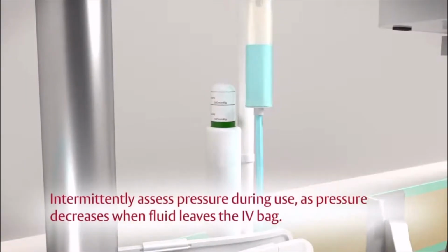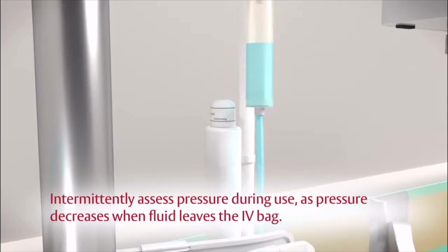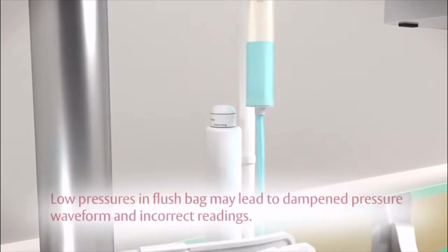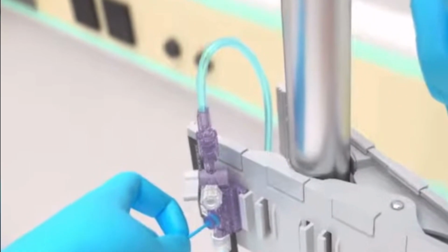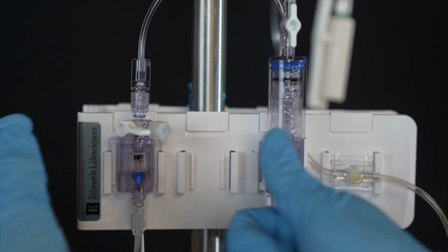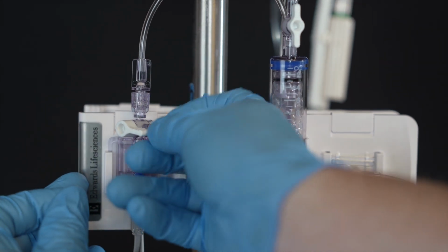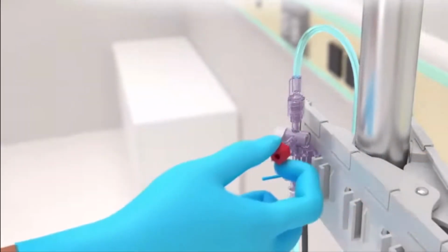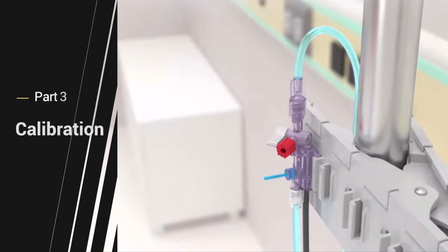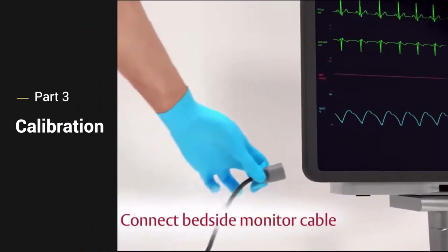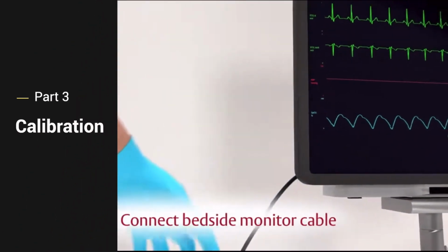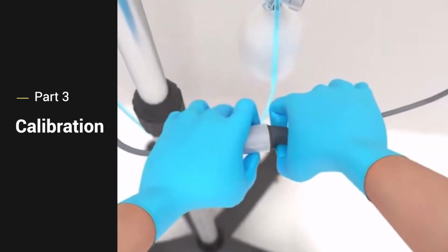Make sure you're intermittently assessing the pressure during use, as pressure decreases as fluid leaves the bag. Low pressures in IV flush bags can lead to dampened waveforms and incorrect readings. Pull the snap tab to flush the system under pressure while tapping on the tubing and stopcocks to remove any residual bubbles. Replace all the opaque vented caps on the side ports of the system's stopcocks with non-vented caps. Use the appropriate connection cable to connect the patient's bedside monitor to the TrueWave's white cable.